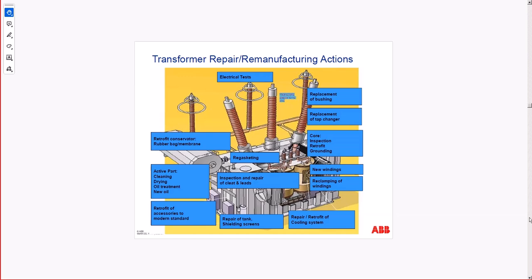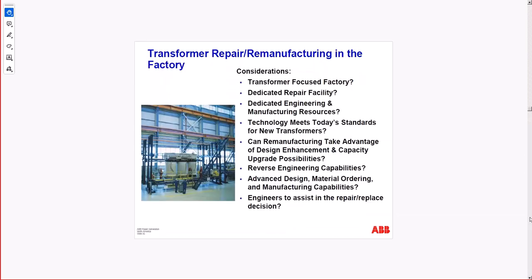Transformer repair. Here are the replacements we talked about: tap changers, cleaning, drying, new oil, repair of the tank, shields, retrofit, modernization, gaskets. Everything that's a gasket, we know they crack. Make sure the gaskets you put in are not at the end of their life, because if you keep a gasket in storage for too long, it is actually unusable. Anything that is not crystalline or metallic and does not have a fixed shape, that is flowing, like plastic, rubber and stuff like that, does not last too long. They have a shelf life, and they need to be maintained in a certain place with controlled temperature, humidity, and so on, so you can use them when needed.